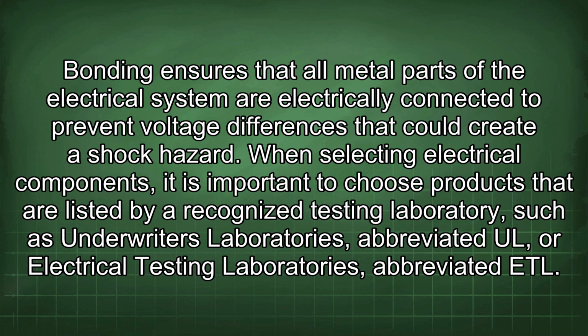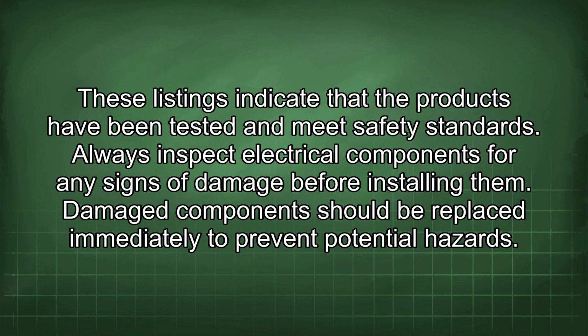Bonding ensures that all metal parts of the electrical system are electrically connected to prevent voltage differences that could create a shock hazard. When selecting electrical components, it is important to choose products that are listed by a recognized testing laboratory, such as Underwriters Laboratories, abbreviated UL, or Electrical Testing Laboratories, abbreviated ETL. These listings indicate that the products have been tested and meet safety standards. Always inspect electrical components for any signs of damage before installing them. Damaged components should be replaced immediately to prevent potential hazards.